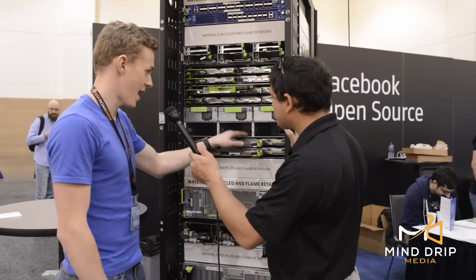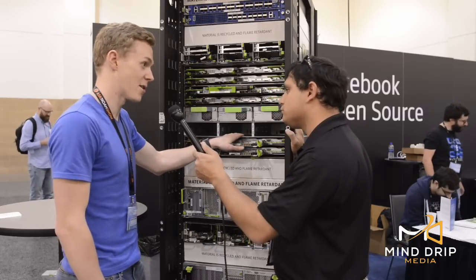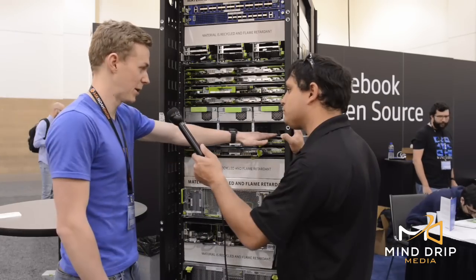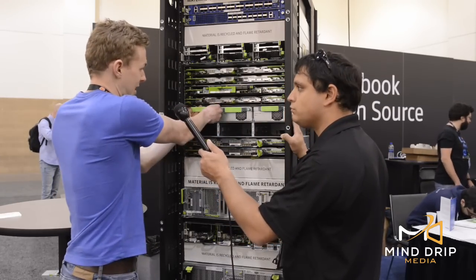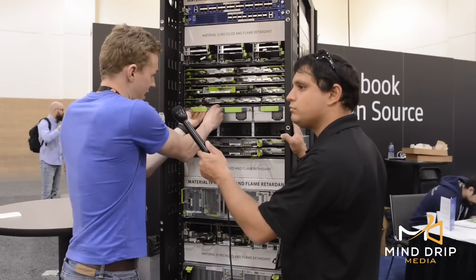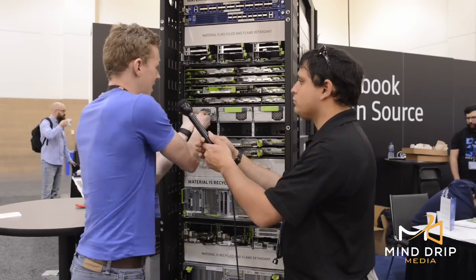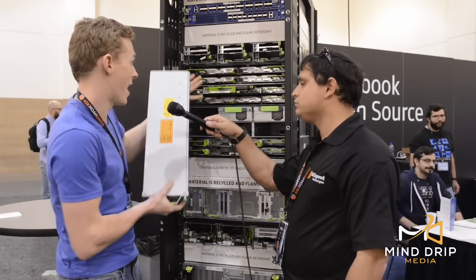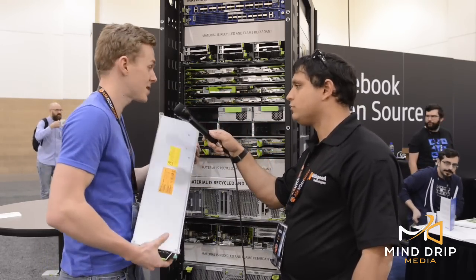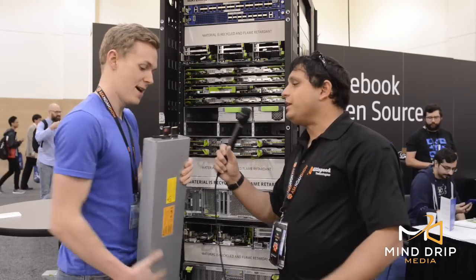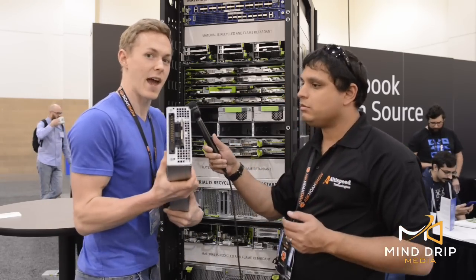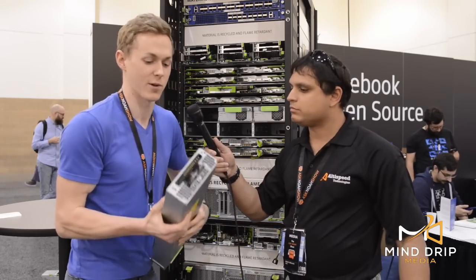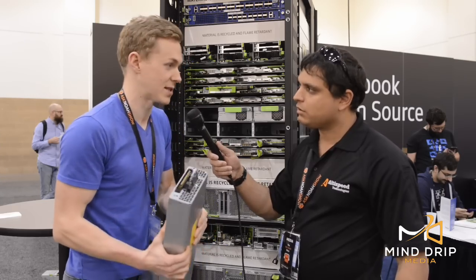So you can actually see on here, they haven't included the battery units, but they are required to run a rack. And you'll see there are actually labels on the front. It may be too far away, but they put the batteries below the power supplies. And we can actually take these power supplies out without any tools, like everything else on the rack. And it's a giant monster of a power supply that supplies power for, I don't know, maybe 15, 20 machines between all three of these power supplies. Yeah, on the back you can see the hefty busbars, because they have these huge metal rods that go to the 12-volt rails in the rack, and then you can see some of the inputs there as well.